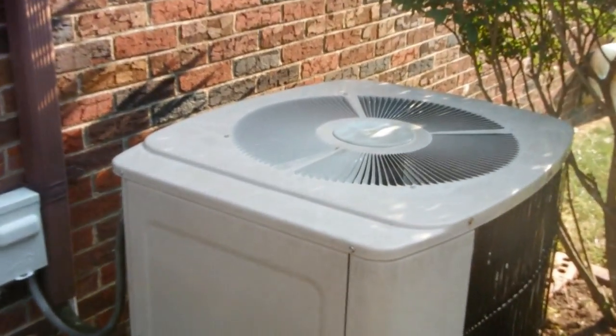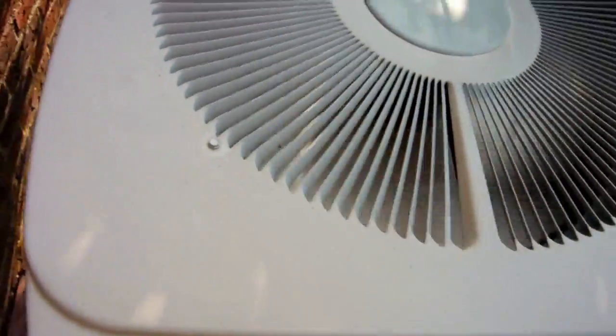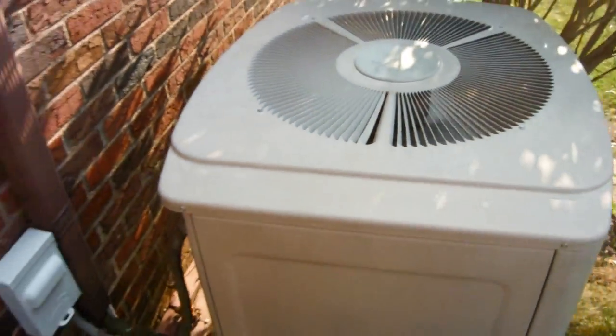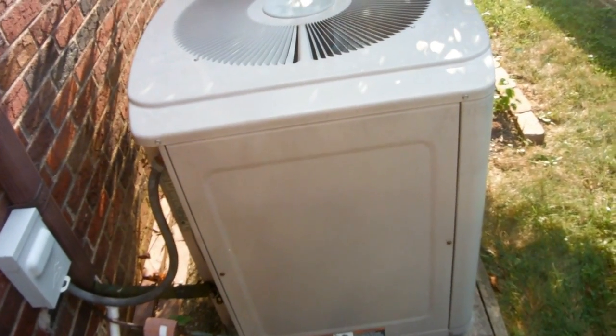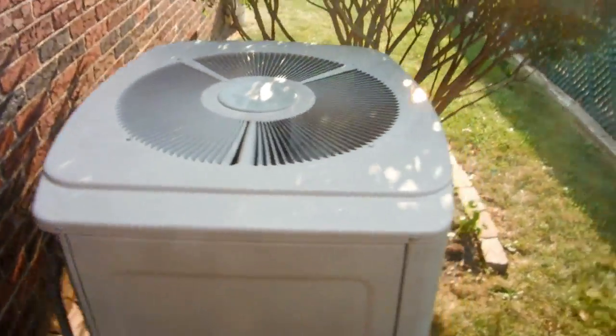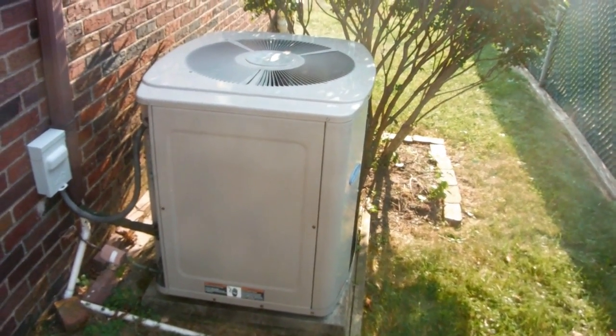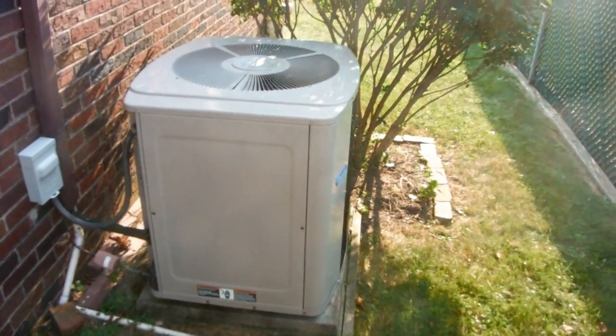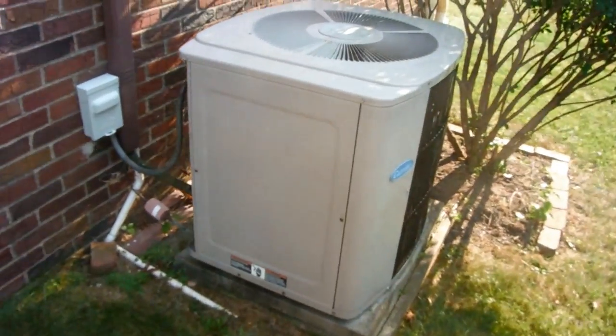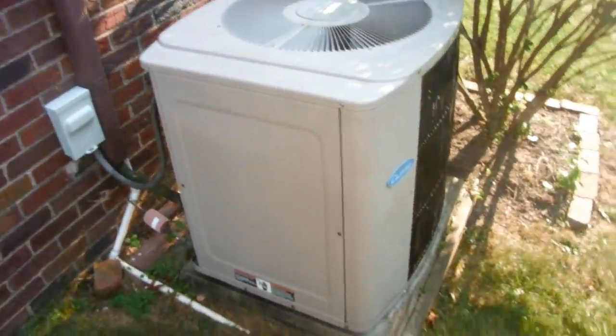That's a Carrier Tech 2000 two-ton central air conditioner, straight cool. I don't know what kind of compressor it has — wait, this has a scroll? I thought some of the older Carriers had reciprocating. Yeah, it's quiet enough that it might actually be a scroll. I know they used Copeland reciprocating and Copeland scrolls in these Tech 2000s. This probably has a scroll in it — the only reason I doubted that is I've seen newer ones with reciprocating compressors, but yeah, this sounds like a scroll.